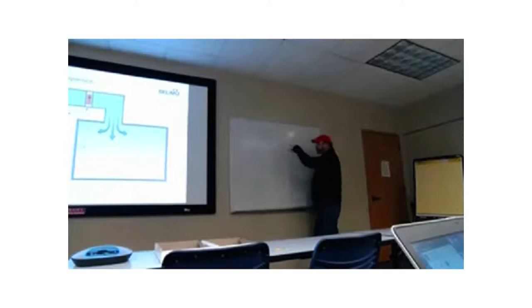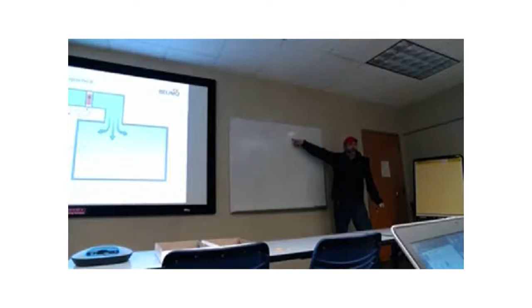So inside the controller, there's actually a couple processes that occur. The one thing is, we call it error summation. So what happens is, the controller looks at the set point, and it looks at the value of the measured variable, the process variable. It comes up with an error signal. Then it goes into this thing called, how about PID? So these are the settings within the controller that basically establish how it responds, right? Are you guys familiar with what I'm talking about here? So you have different values of proportional and integral and derivative. Well, in HVAC, we don't use D so much. We use proportional and integral. And then most of our loops are accommodated by those two responses.